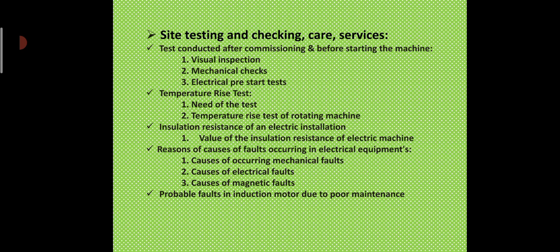Now, causes of electrical faults. Causes of puncturing in insulation include prolonged overvoltage, overheating, cut or scratch in the winding, shaft bearing or in the winding, aging of the winding, etc. Causes of short circuit in the winding include worn out insulation, overloading, and carelessness during maintenance. Causes of loose connections include excessive vibrations, not using the spring washer, and insufficient force while making connections.